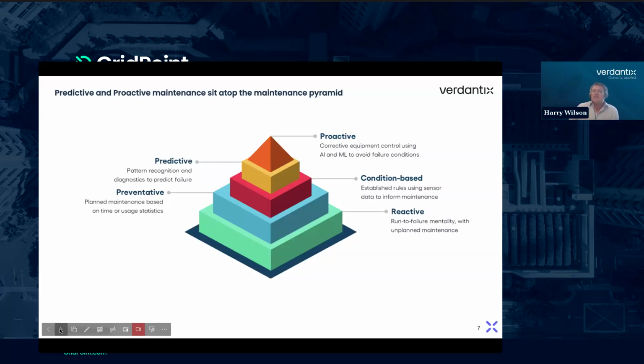Now, condition-based maintenance goes one step further. This might be more about actual rules which apply to the equipment. So going back to that air handling unit example, the pressure drop over my filter on the air handling unit has reached a certain amount, so I know it's time to change the filter, or clean it. That's really the condition that then drives the maintenance activity.